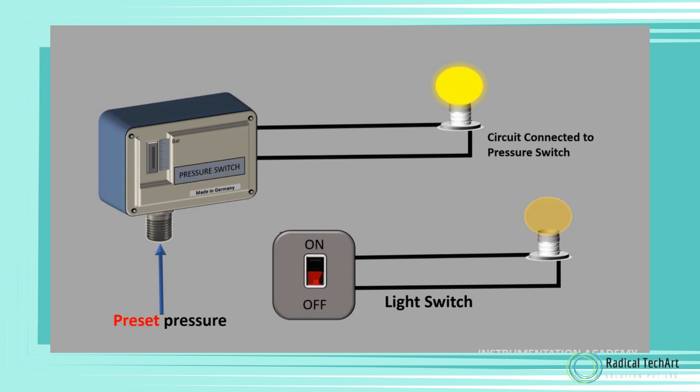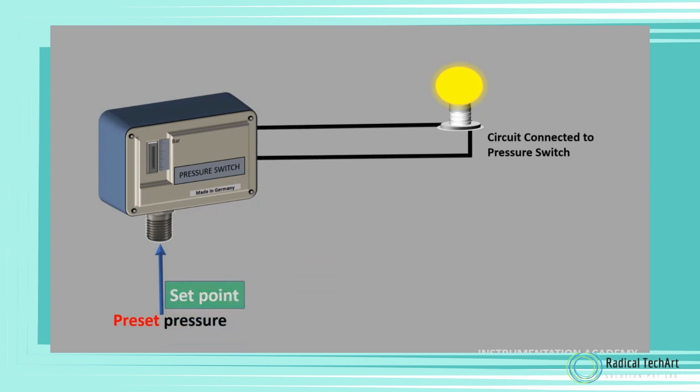In the case of a pressure switch, instead of being manually switched, the switch closes or opens the contact when the input pressure reaches above or below a preset value. This preset pressure is known as the setpoint of the pressure switch. The output of the pressure switch is digital, which means the output can have only two states: on or off.